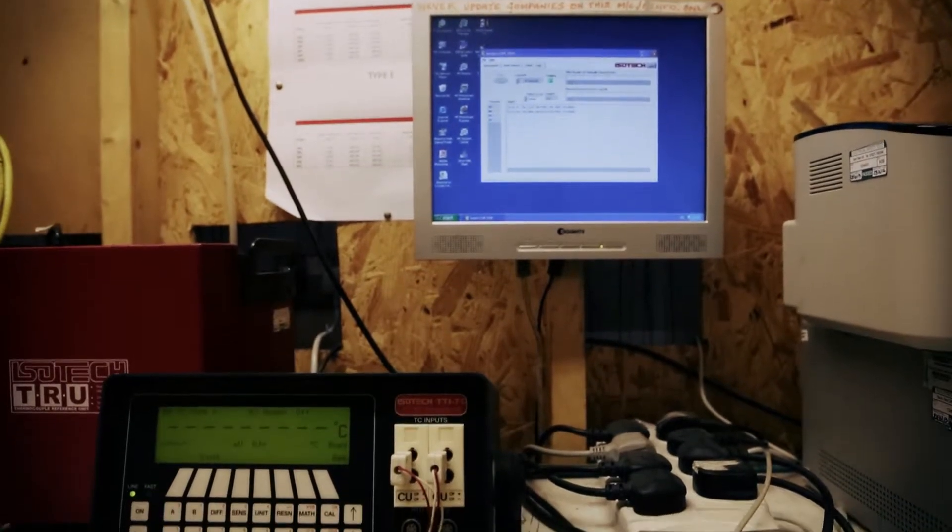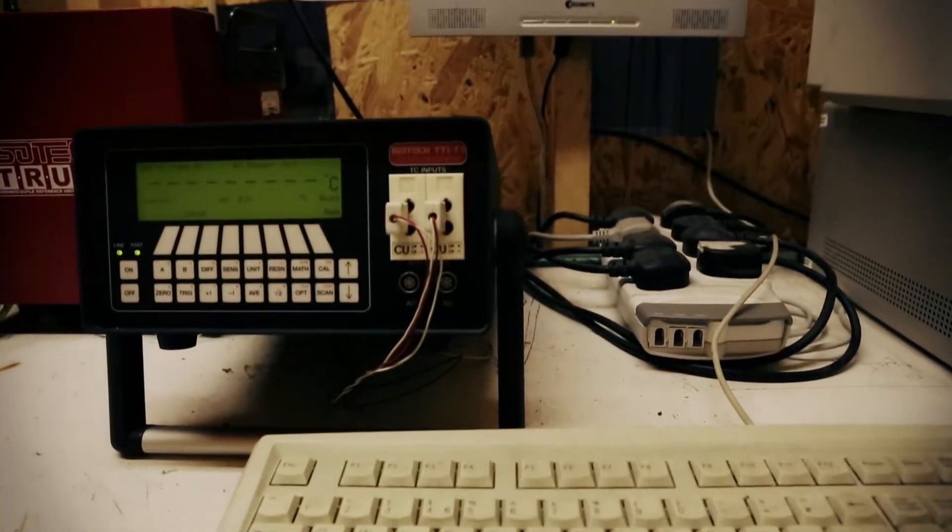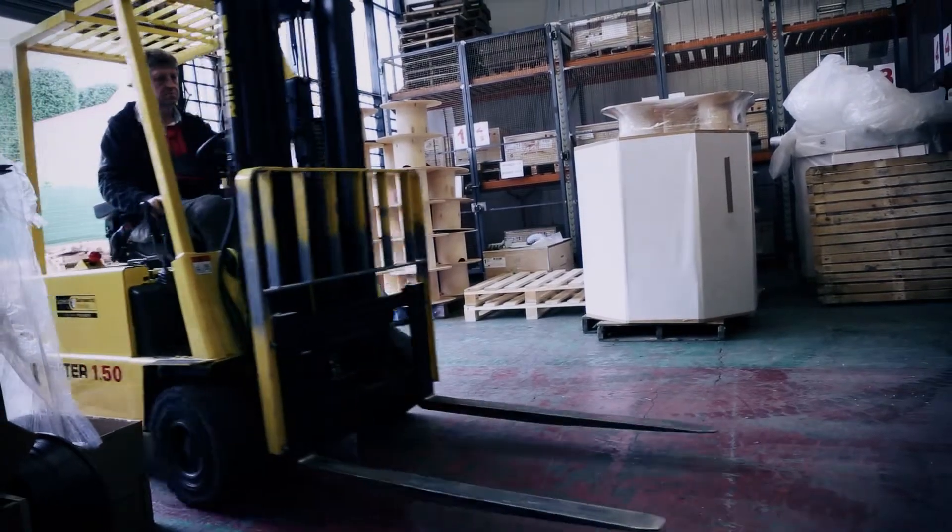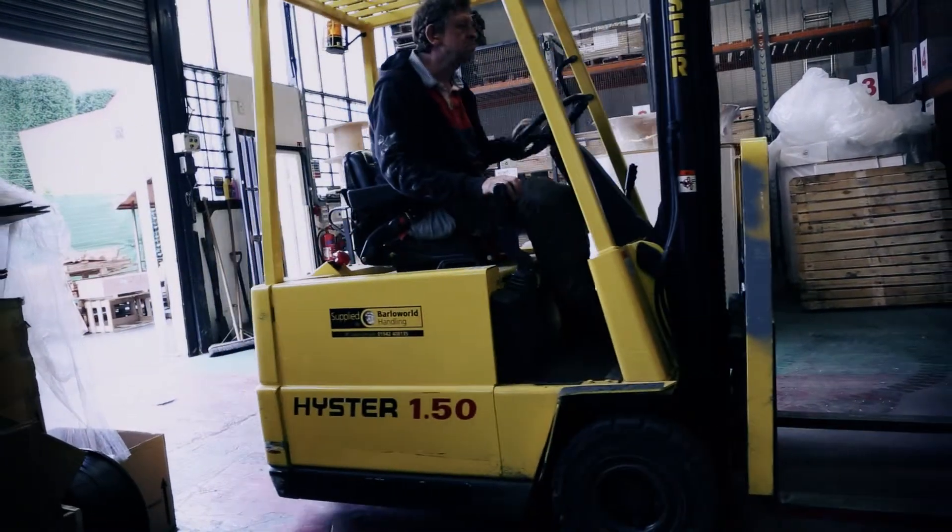The final check is a computer controlled EMF test to ensure the thermocouple cable meets the required international standards. All products are tested through the cable's operational temperature range, a test that can take eight hours to complete.